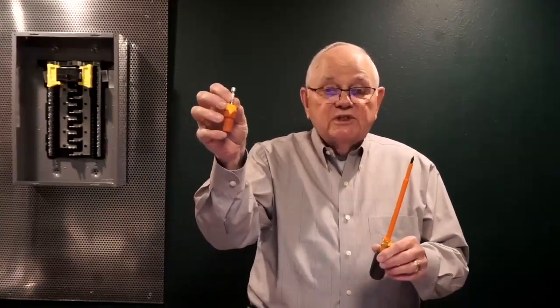So back to our requirements on the shock risk assessment, we identify the hazards. And then the second thing we have to do is ask, what is the likelihood that I'm going to be injured by this hazard, assuming that I follow safe work practices and wear the appropriate PPE? And then number 3 is, what am I going to do about it? What steps am I going to take in order to mitigate this shock hazard? So the things that I can do, just like we talked about at the beginning of this tech talk, I can create an electrically safe work condition, lockout, tagout. I can wear my insulated rubber goods, my insulated rubber gloves for shock protection. I can use insulated tools as needed for secondary shock protection then.